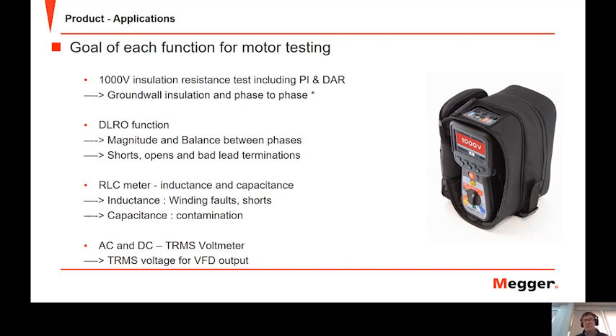The DLRO test, or the Kelvin resistance test, we're looking for the magnitude of the phases, but also the balance between the phases. And this can indicate short circuits, open circuits, and also bad lead terminations or connections. The LCR meter provides us with the inductance and capacitance. And as we said in the previous slide, inductance can help us detect winding faults, such as a reversed phase. And that's something that winding resistance cannot do. And I can show you that later.